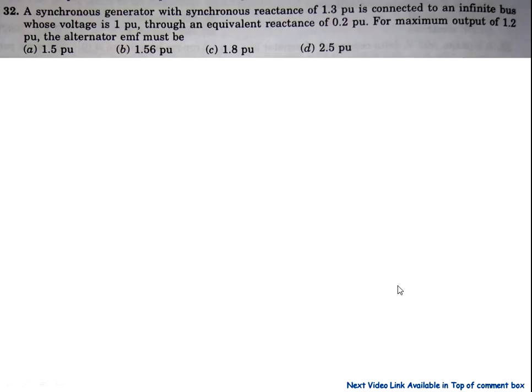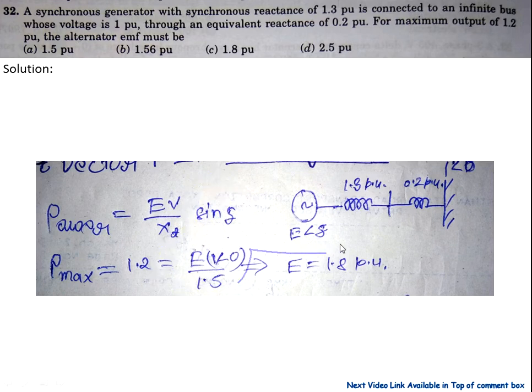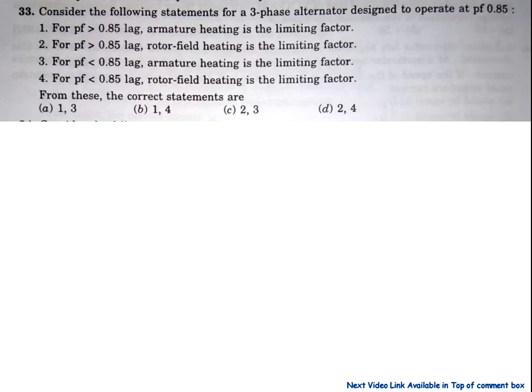Now come to question number 32. A synchronous generator with a synchronous reactance of 1.3 per unit is connected to an infinite bus whose voltage is 1 per unit, through an equivalent reactance of 0.2 per unit. For a maximum power output of 1.2 per unit, the alternator EMF must be — these are the options. The power equation is E·V/X, and for maximum power, sin(delta) equals 1 at delta = 90°, giving E equals 1.8 per unit. So option C is correct.